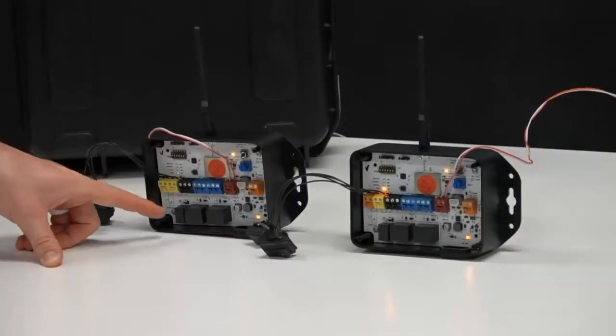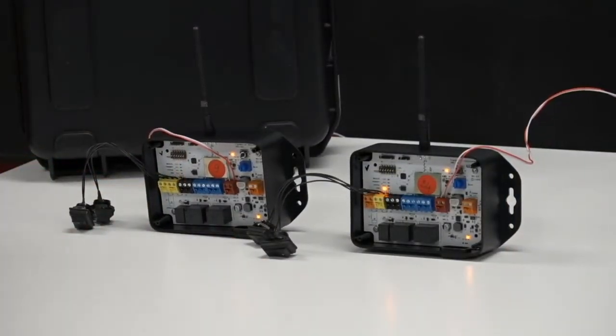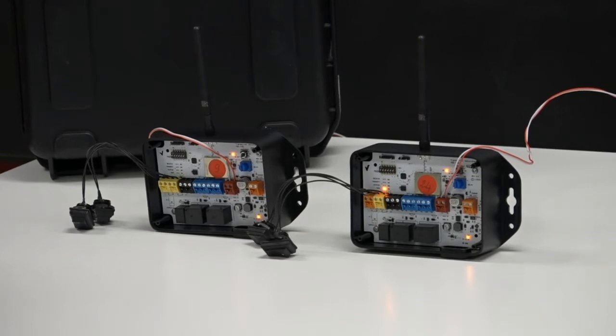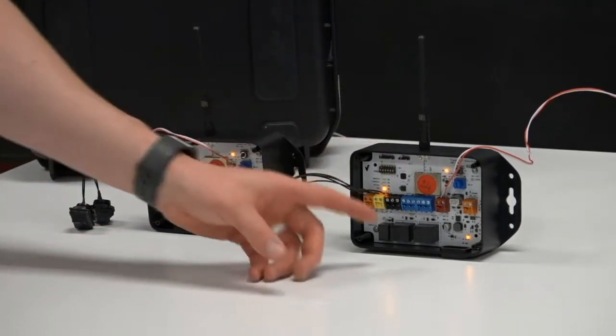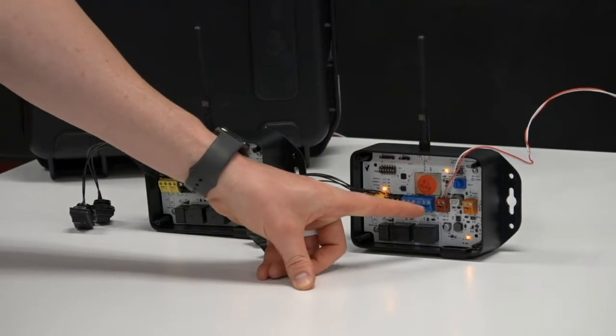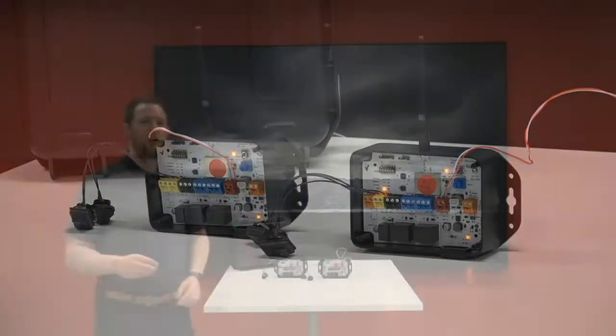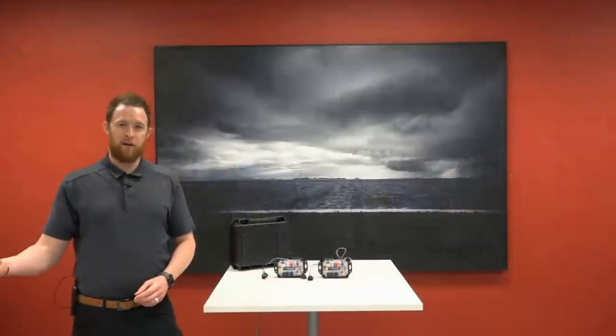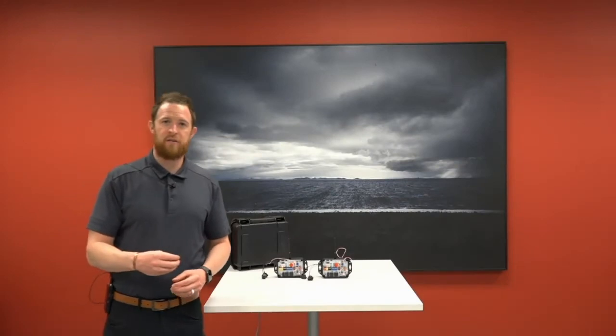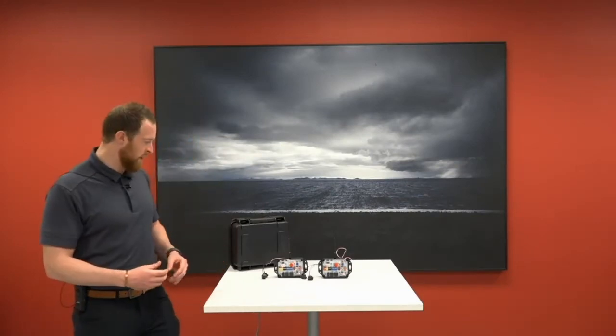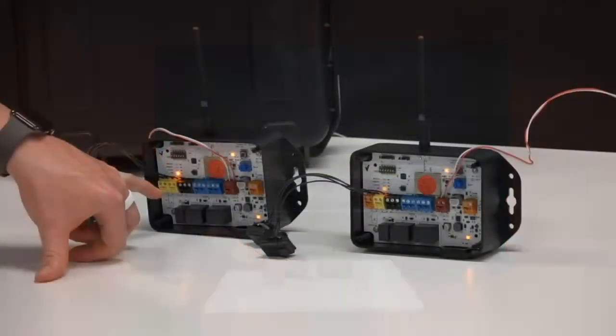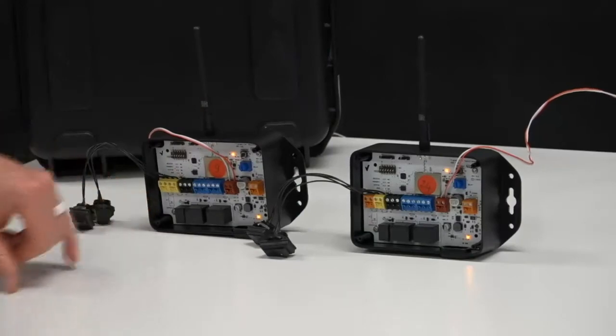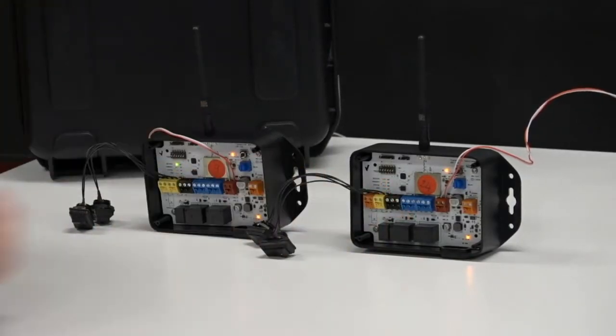So you would wire the telephone entry relay output to our yellow terminals. Yellow is our input. That means where we are receiving the output from whatever device the wire has been damaged on. And then you're going to take the other device and you're going to wire up our output, the blue terminals, to whatever you are triggering, which in this scenario is the gate operator because the wire has been damaged.